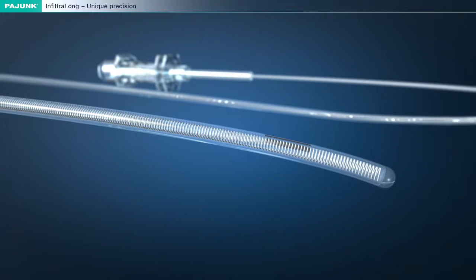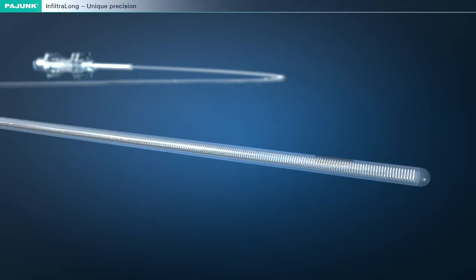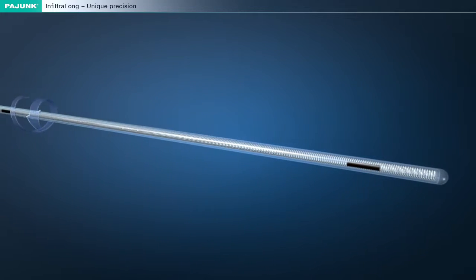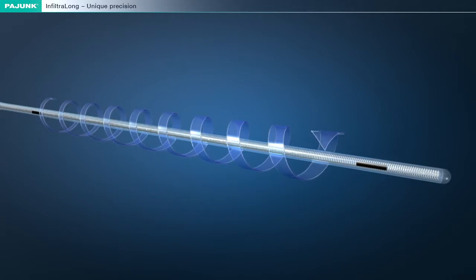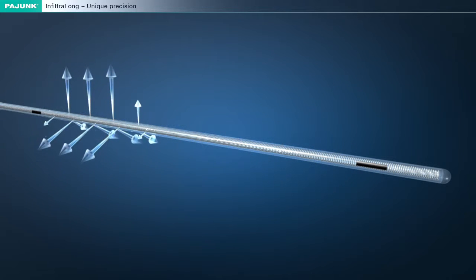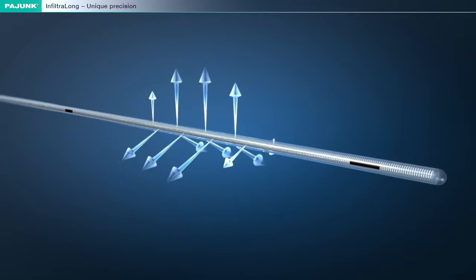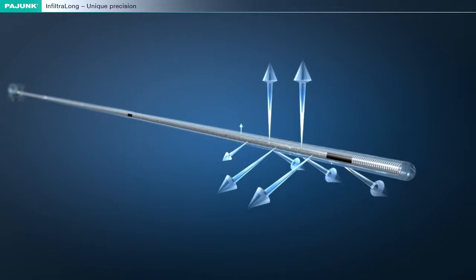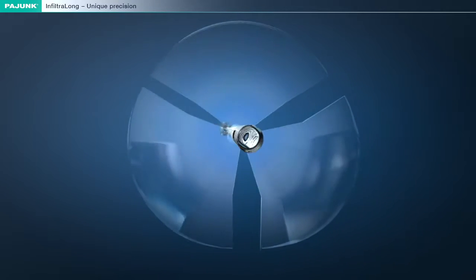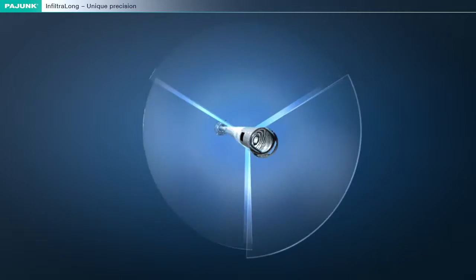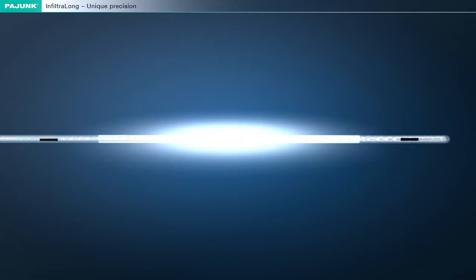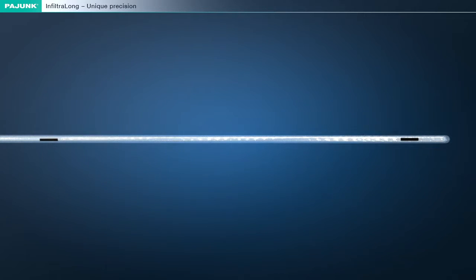The construction of the catheter is unique. It has been provided with an array of micro-perforations arranged in a spiral line running along and around the catheter. Both the diameter and the spacing of the perforations are characterized by absolute regularity and utmost precision. We can therefore achieve a precise and uniform 360-degree distribution of the anesthetic. The beginning and the end of the perforation have been provided with markings to ensure that the perforated segment of the catheter can be placed in the incision along its complete length.